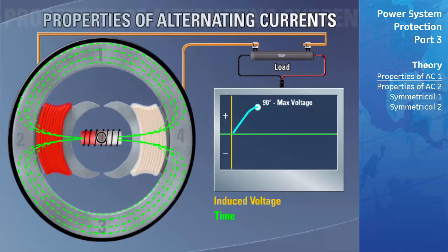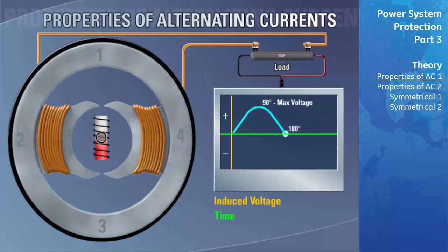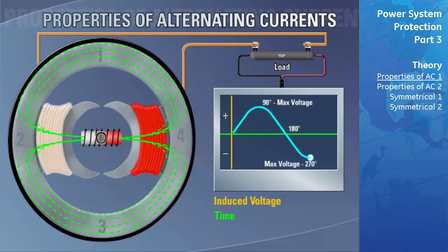The two stator windings are connected in series such that voltages induced in each winding add together and appear across the load. At position two, the maximum number of lines of flux from the exciter's field are cutting the stator windings, corresponding to a peak in the induced voltage. As the north pole continues rotating toward position three, the number of flux lines decreases, resulting in a reduction of induced voltage. Once the exciter reaches position three, no flux flows through the stator poles, resulting in zero induced voltage.